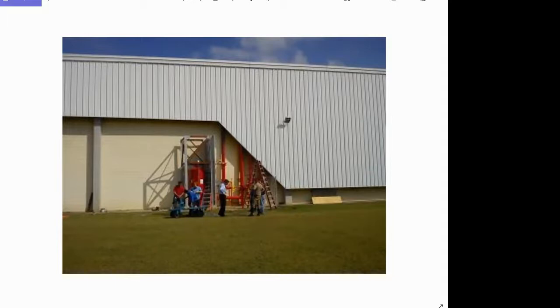They got introduced to the F500 encapsulator agent from our Brazilian partners. We set up sprinkler systems and tested plain water versus, I don't remember if it was 1% or 3% F500, on their commodity with the local fire department as authority having jurisdiction. The result: water failed miserably, while F500 put the fire out, and we could hand these parts to the authority having jurisdiction because they were cool to the touch. They approved the product because we were flowing at the exact same densities.